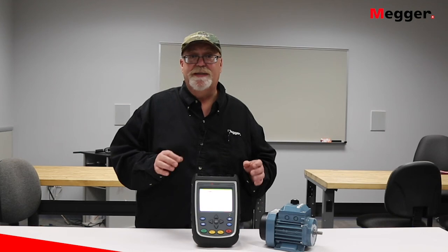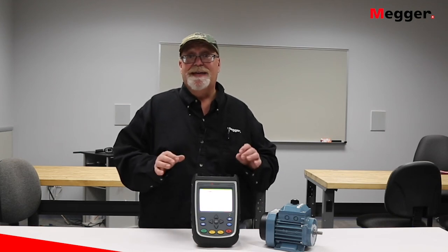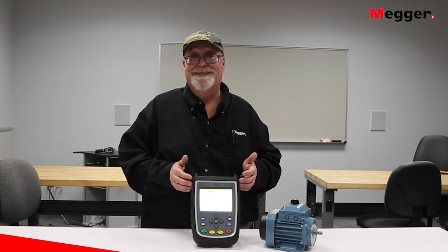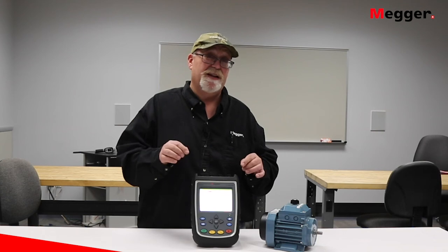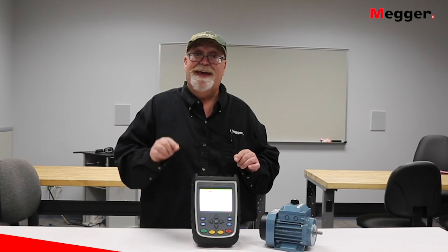Characterizing inrush currents and their effects requires a monitor that can capture the waveforms for long durations. Most monitors today cannot do this. The MPQ can capture inrush waveforms for over 10 seconds, and that's on every channel simultaneously. In addition, the MPQ can monitor the motor for days or weeks at a time, and it will capture that inrush current every time that motor starts.